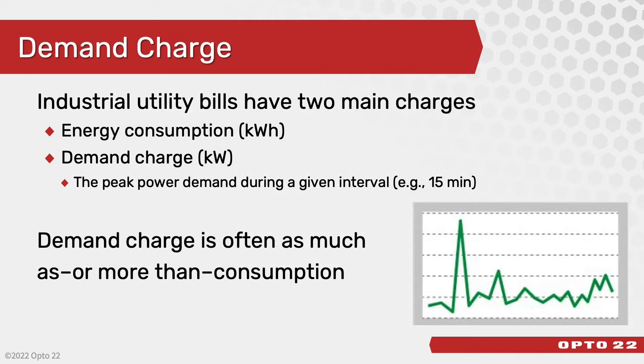Let's take a minute to talk about the energy bill. For medium and large industrial customers there are typically two components. One is consumption in kilowatt hours — that's the amount of energy used during the billing period. The other, which many people are unaware of, is called demand charge. That is a tariff applied to the peak power in kilowatts used during the month. It's usually measured in 15-minute intervals, and that highest value is taken and applied to the whole month. That demand charge is often as much as or even more than the consumption charge.